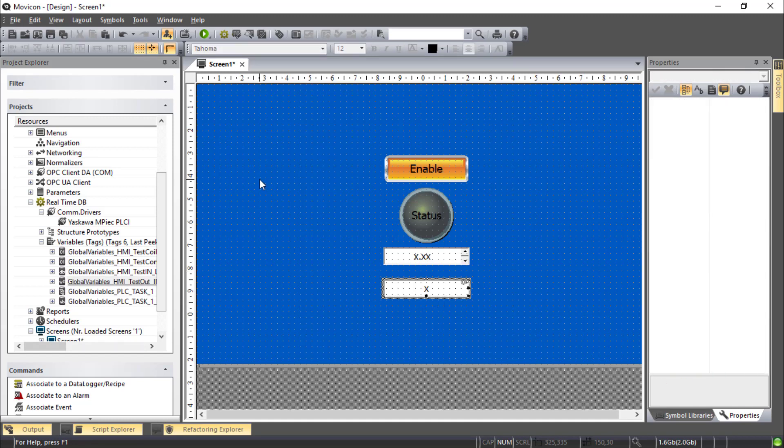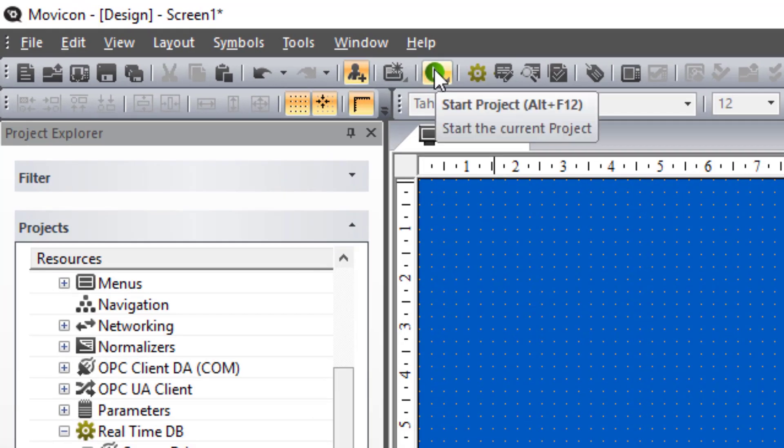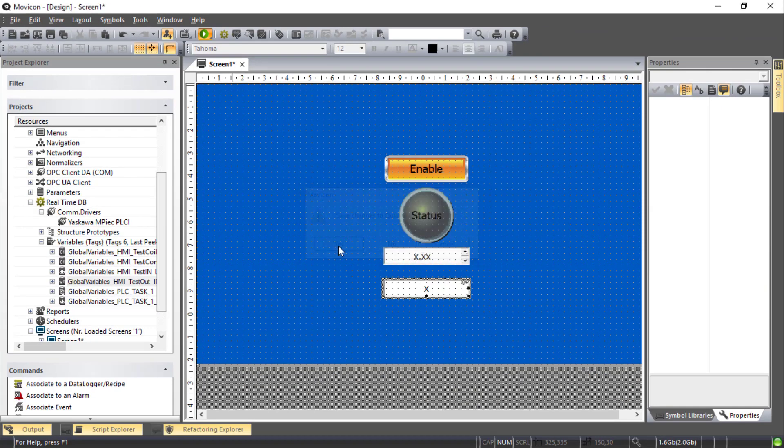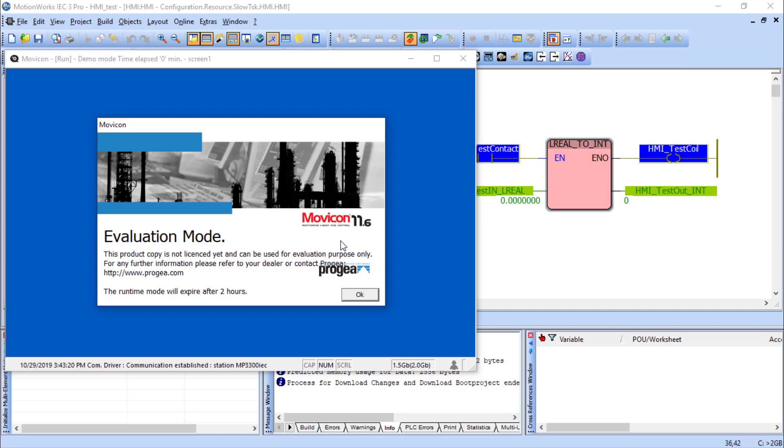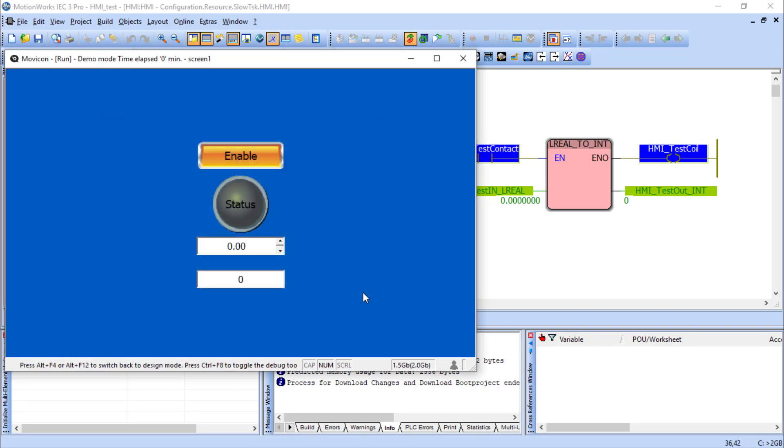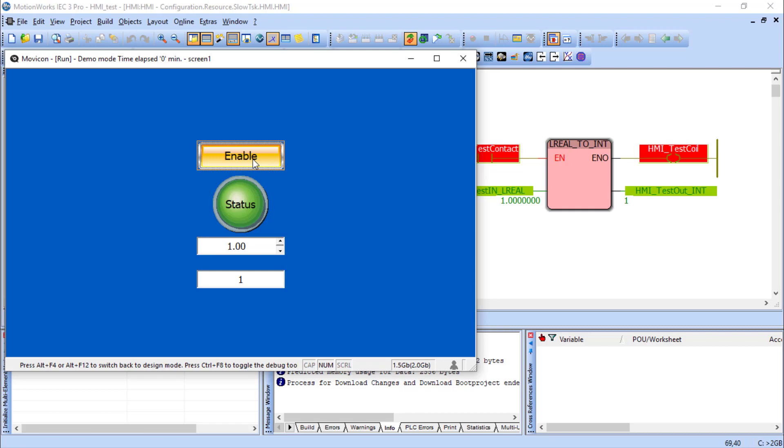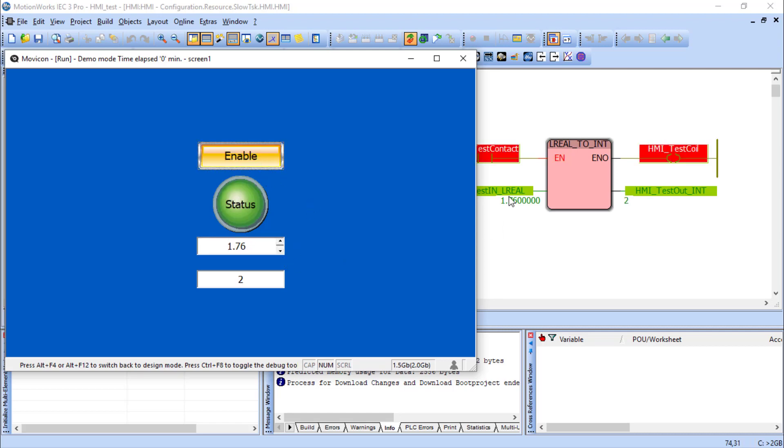So before we send this to the physical HMI we can test it right here in Movicon using the simulator. Called Start Project. Yes, you want to save. This launches the on-screen runtime simulation. You click OK to accept that. And let's test it out here. Hit Enable. The code sees that. And status reflects that. If I try to increase the value here, it's reflected in the controller. And Enable moves that over. Converts it to an integer. I could try to put in a different value and see what happens there. Seems to be working.